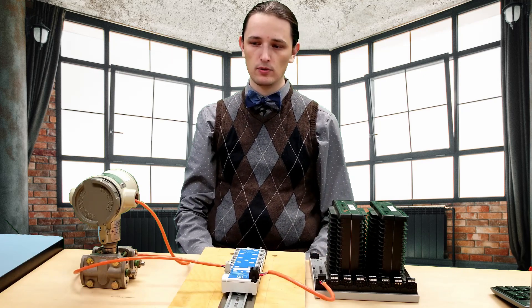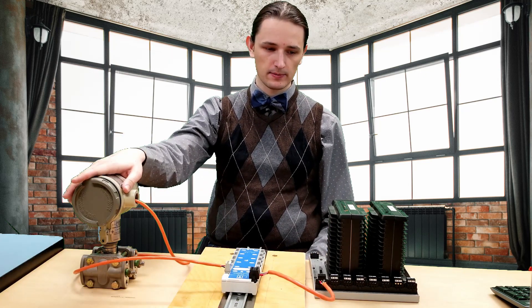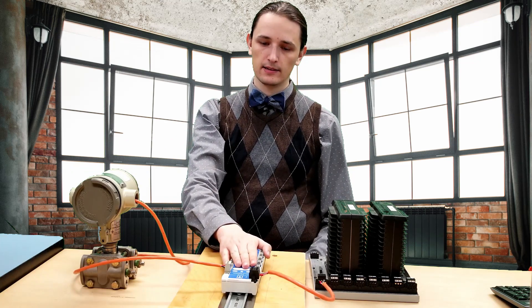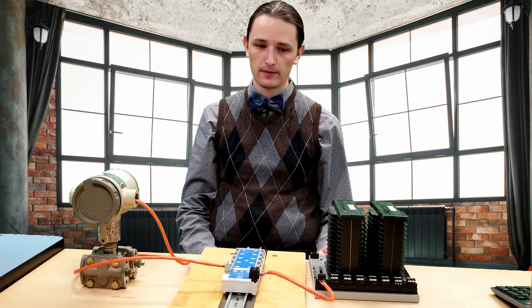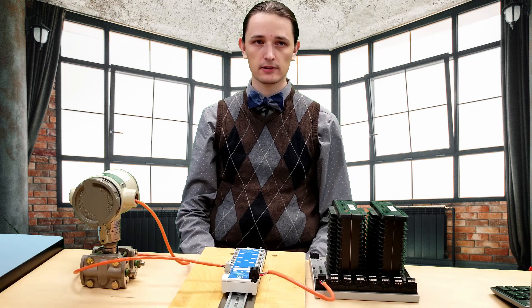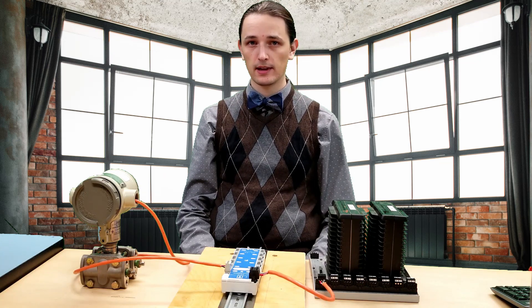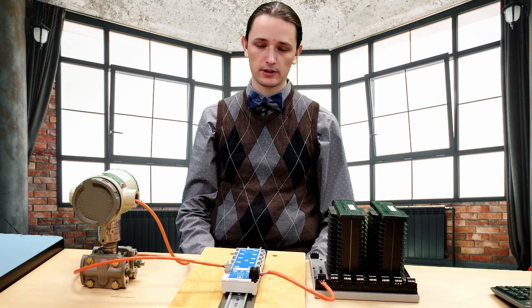It's important not to ground at two points, for example at the instrument or at the device coupler in addition to the power supply, because the differences in ground potential throughout the plant could lead to current flowing through the shield, introducing noise in the segment, defeating the purpose of the shield.